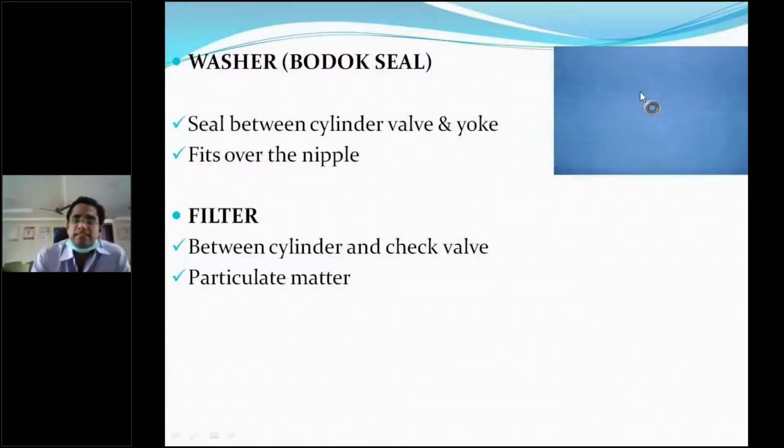As I told you, this is the washer, also known as the Bodok seal. What is the importance of the Bodok seal? It is the seal between the cylinder valve and the yoke. It fits over the nipple. You have a filter between the cylinder and the Bodok seal to filter any particulate matter from the oxygen cylinder entering the anesthetic machine.